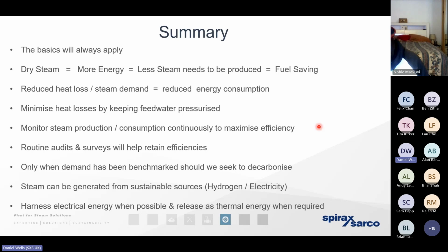So, as I've mentioned, we've taken those 3 steps ourselves. We've completely removed gas from our facility in Cheltenham. We've got a steam battery in place to take into account those maximum instantaneous surges and demands for steam. We've electrified one of our existing steam boilers, and we've completely replaced one of the older boilers and put a brand new steam generator in place. So the 3 technologies that I've spoken about in some detail have all been engineered and installed down at our facility in Cheltenham. We've actually turned off our natural gas. We've got fully electrified, decarbonised steam.